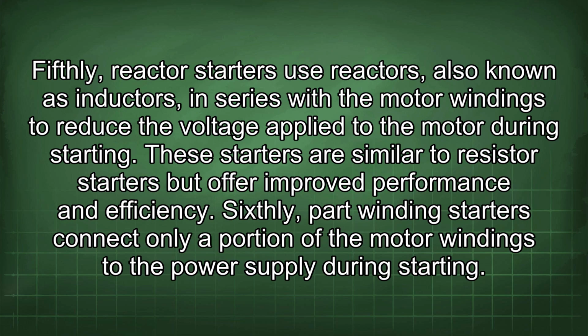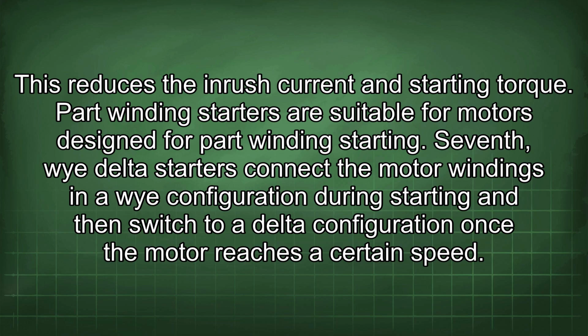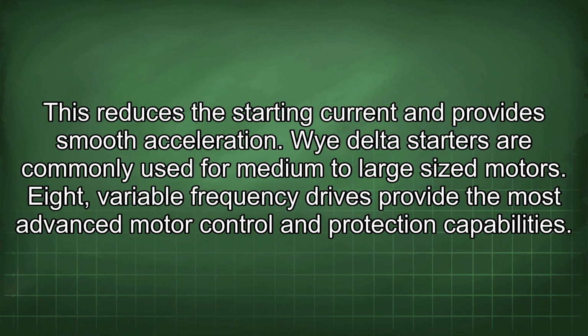Sixthly, part winding starters connect only a portion of the motor windings to the power supply during starting. This reduces the inrush current and starting torque. Part winding starters are suitable for motors designed for part winding starting. Seventh, Y delta starters connect the motor windings in a Y configuration during starting and then switch to a delta configuration once the motor reaches a certain speed. This reduces the starting current and provides smooth acceleration. Y delta starters are commonly used for medium to large size motors.